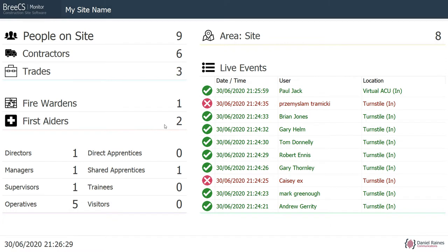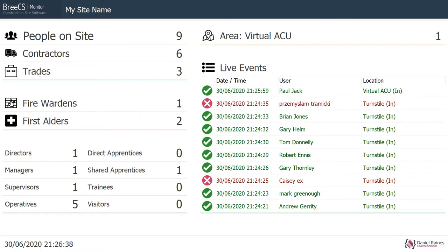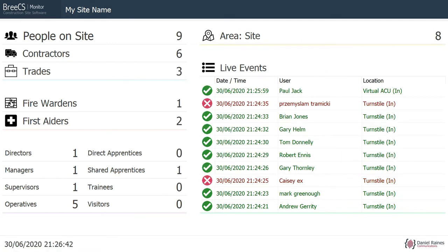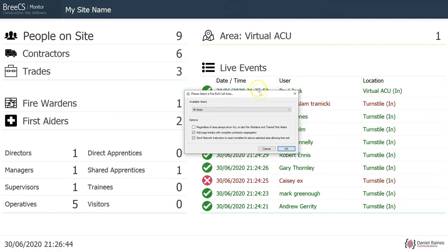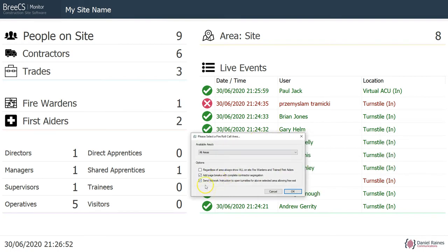The next thing I'll do is just show you the fire alarm integration. Within the BreeCS software, if you generate a fire roll call report — I've got the software open on another screen — if you generate a fire roll call report and you've got 'send network instruction' ticked, then that will send network instructions to open all turnstiles and will flag up a message at the bottom to say that the fire alarm has been activated.